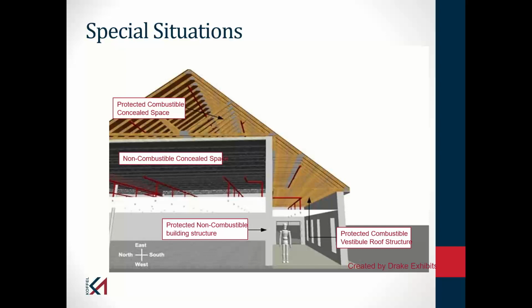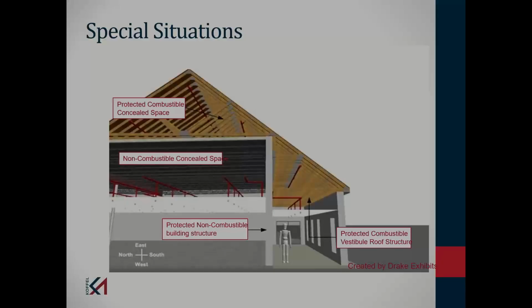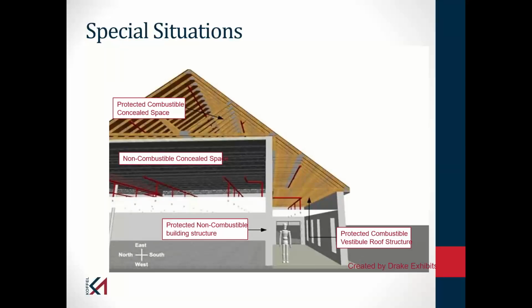So on the slide, we see a non-combustible concealed space. Steel building, lay an acoustical tile or gypsum wallboard or something as a ceiling membrane. Yes, you may have some data cable up there. You may have some power conductors up there, but there's not enough up there that's going to cause the fire to spread throughout that space. We don't need to put sprinklers in that space.